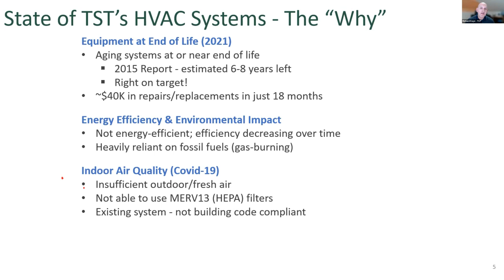This was right in the height of the pandemic, and there were several things that really concerned us. I was also on the COVID task force at the time, and I learned very quickly that our existing HVAC system did not support the use of MERV 13 or HEPA filters. HEPA is high efficiency particulate airborne filtration, and MERV is just a rating—MERV 13 is kind of the minimum you need to get HEPA level filtration. Older, inefficient equipment can't move air through HEPA or MERV 13 filters, so that was a big issue. The other thing is the old equipment couldn't process any more outside air being drawn into the building, and bringing in fresh outside air is one of the big remediators of indoor air quality.